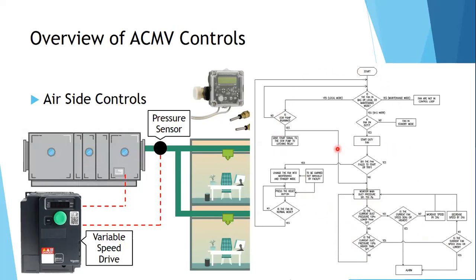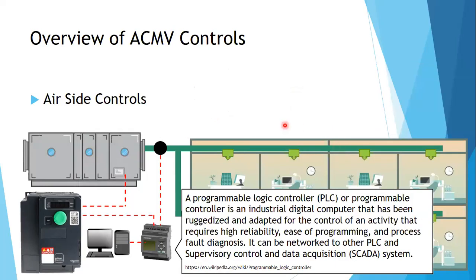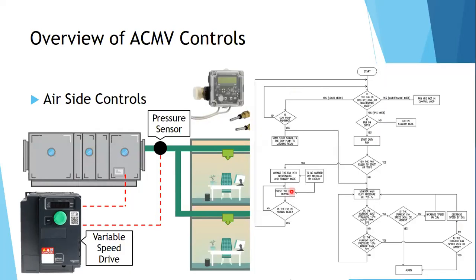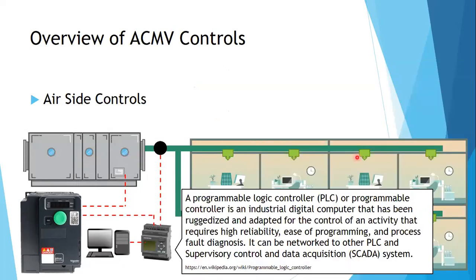Now, this control logic is located inside your PLC. So what is a PLC? A PLC is a programmable logic controller. It's basically a small computer where you put your logic in. So all this logic, all this decision making, all these conditions, all this monitoring, and the appropriate action or appropriate decision that needs to be made are stored in a PLC. So this PLC is standalone. Your pressure sensor is just sending out a signal, and to interpret this signal is the job of a PLC. And this PLC will tell other equipment what to do. So the signal from your pressure sensor will go to a PLC. Then the PLC will evaluate and will tell the VSD what to do. This VSD will tell the motor what to do.